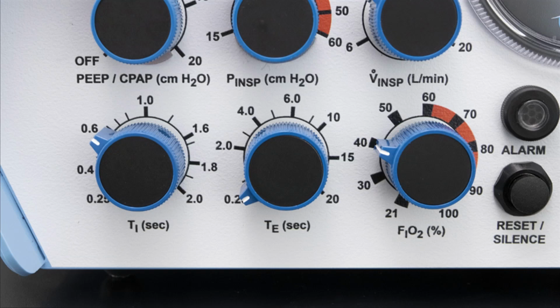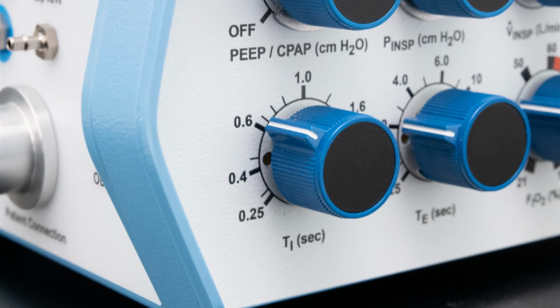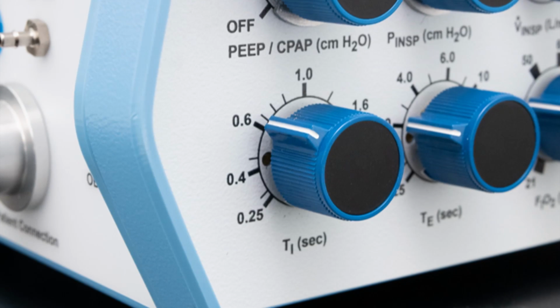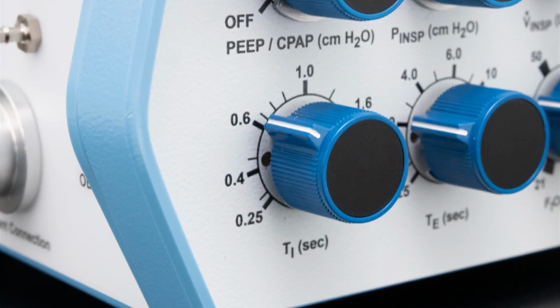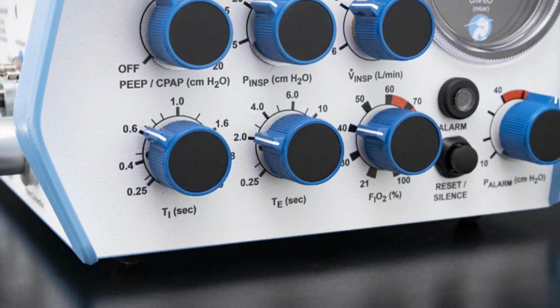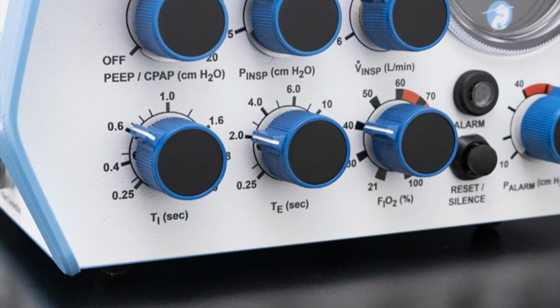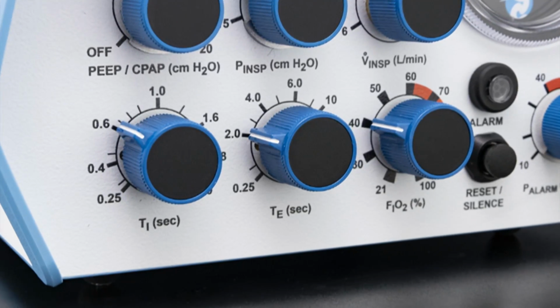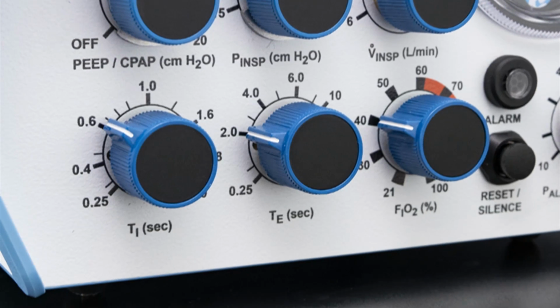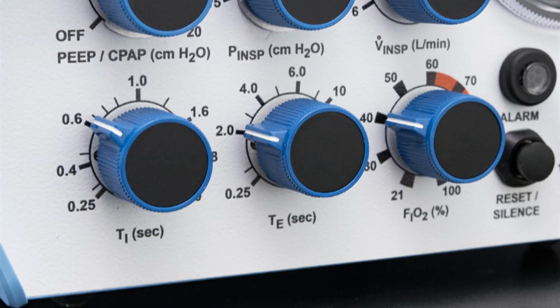For patient ventilation using the IMV plus CPAP mode, the ventilator provides a respiratory rate, or breaths per minute. First, set the inspiratory time, TI, to an appropriate level for the patient. Then adjust the expiratory time, TE, control to achieve the desired mandatory breath frequency. The patient may breathe spontaneously between ventilator breaths as desired.